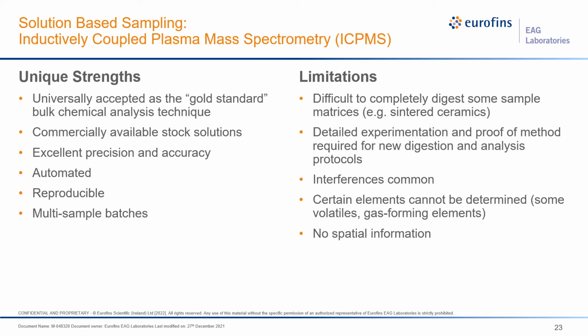Another important concern is the presence of interferences due to polyatomics formed within the ICP-MS instrument between gases and sample matrix, gas interferences directly from the gases used during analysis, natural isotopic or isobaric interferences. Accounting for these interferences is a crucial part of the ICP-MS process, and various hardware and data correction solutions are used to minimize or eliminate their effect on results.